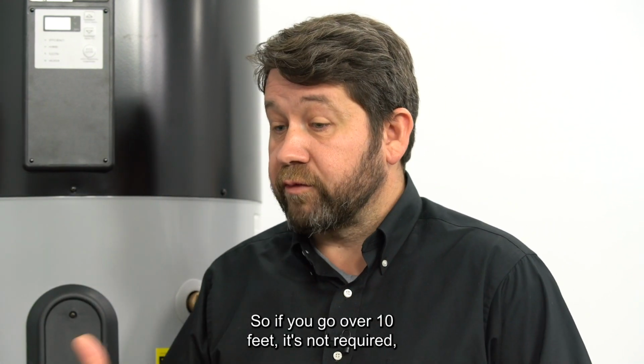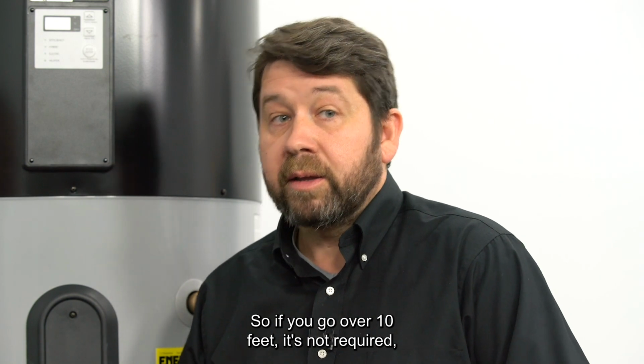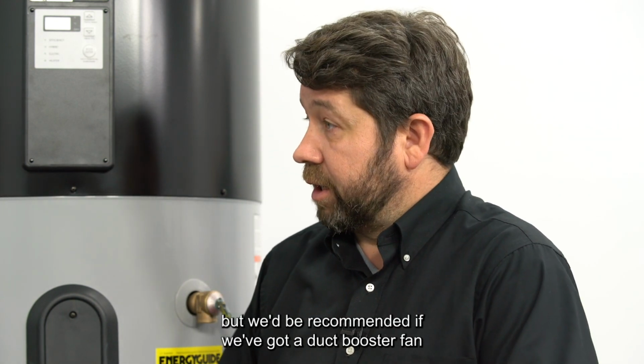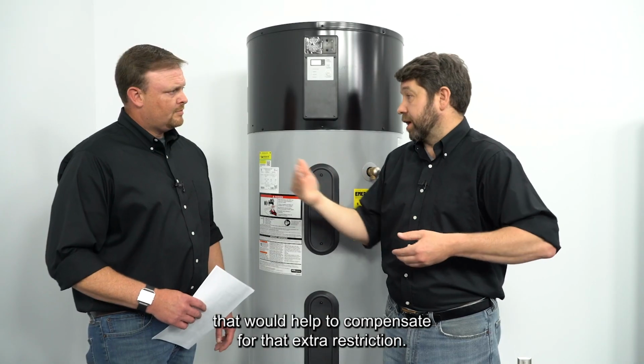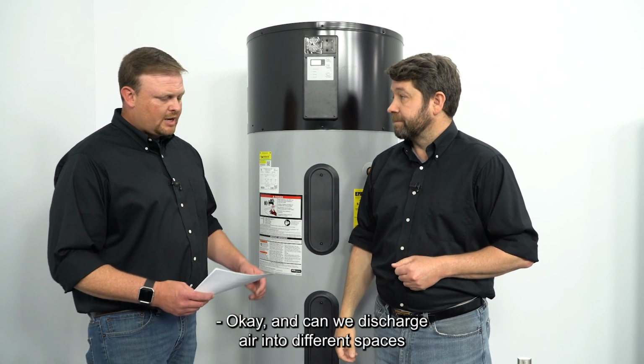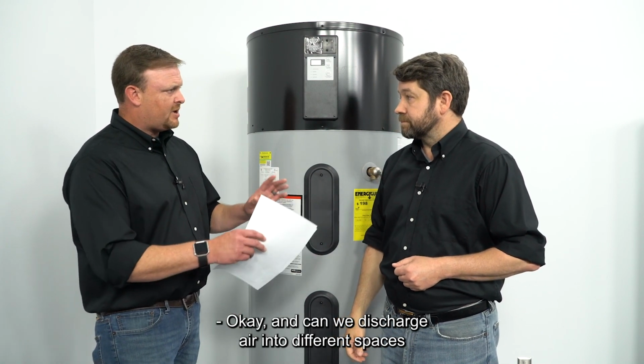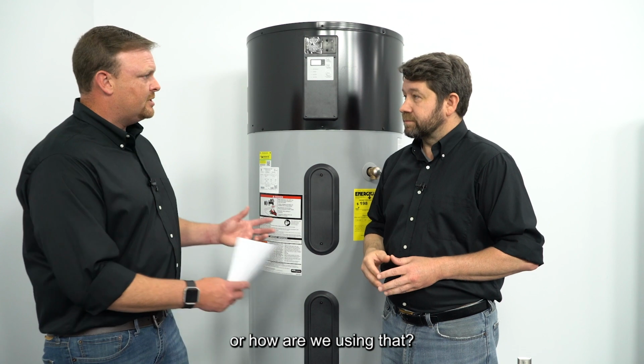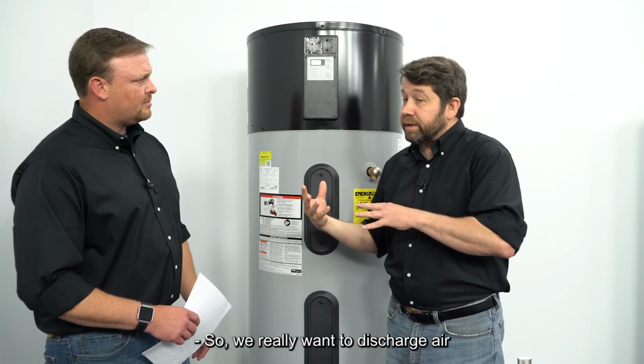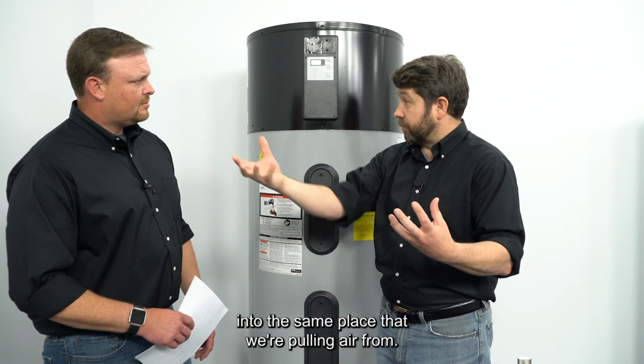So if you go over 10 feet, it's not required, but we'd recommend a duct booster fan that would help to compensate for that extra restriction. Okay, and can we discharge air into different spaces, or how are we using that? So we really want to discharge air into the same place that we're pulling air from.